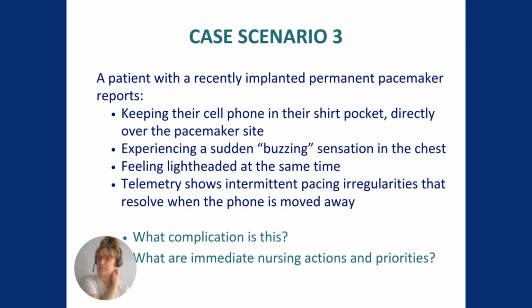In demand modes like VVI or DDD, oversensing can cause the pacemaker to temporarily inhibit pacing because it falsely believes the heart is beating on its own. The patient then experiences a buzzing or fluttering sensation, irregular beats, and lightheadedness. If pacing pauses, the heart may go back to its underlying rhythm, which could be not good.